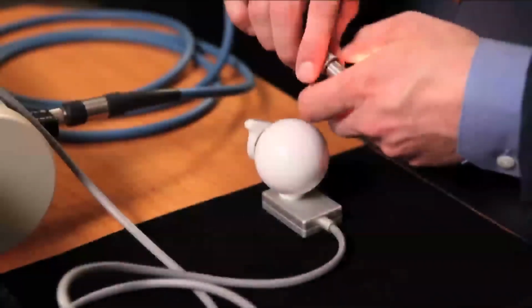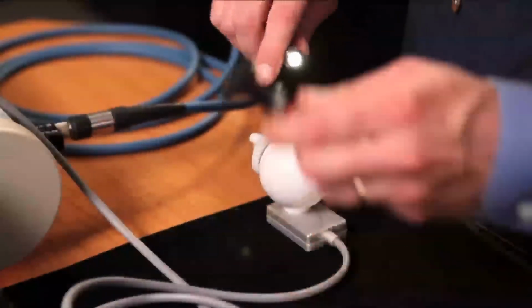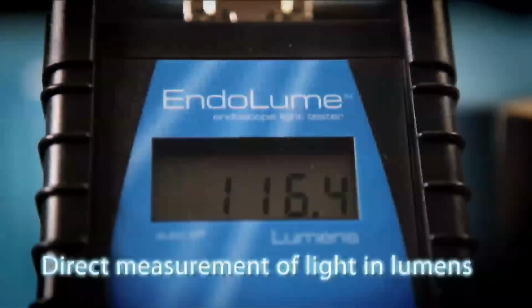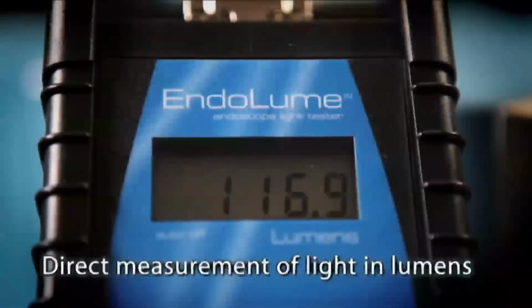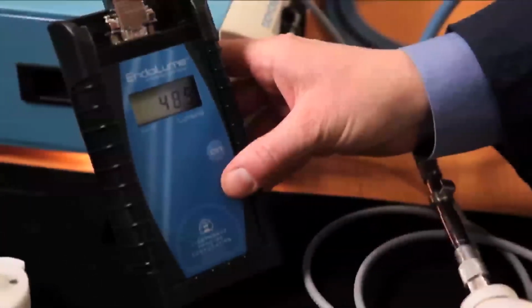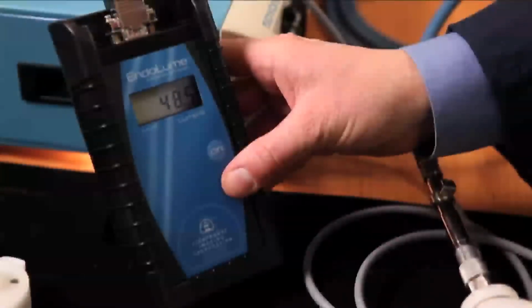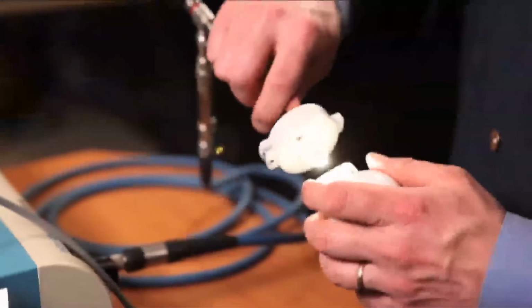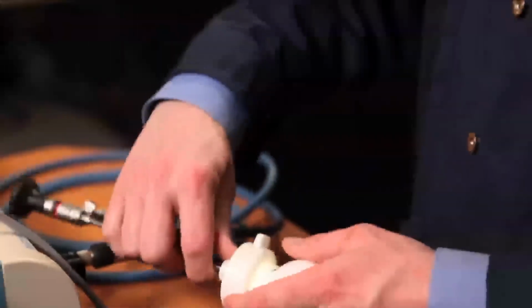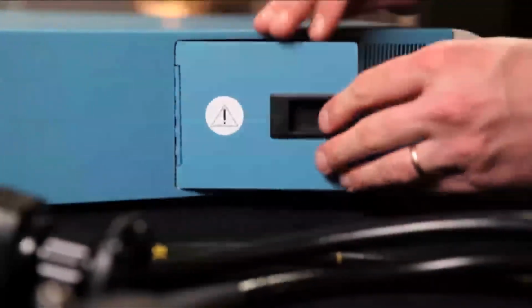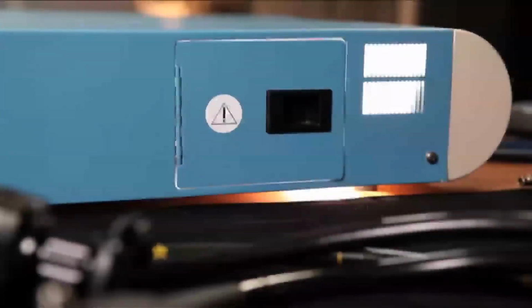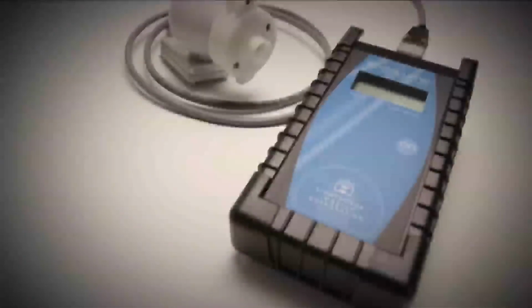The EndoLume's patent-pending optical bridge uniquely makes accurate measurements inside the light source at the exact position of the light cable tip. The EndoLume reads in lumens, a direct measurement of the radiant intensity as perceived by the human eye. With the EndoLume, users can now establish evidence-based quality assurance for the hospital. Engineers and technicians can now use quantifiable measurements to manage endoscopic equipment. With the EndoLume, the biomedical and clinical engineer can quickly isolate the source of an illumination problem and get the clinical staff back in business fast.